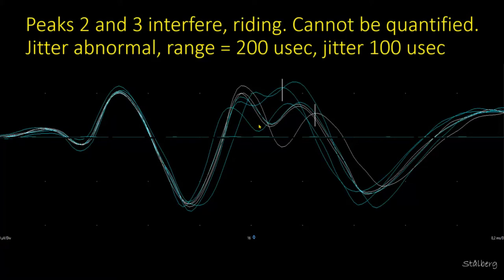Here is another situation where we trigger here with some baseline fluctuation, and the riding is very severe. The first, second, and third peaks are visible. The earliest and latest position of the third signal show a range of about 200 microseconds, which corresponds to a jitter of about 100 microseconds — definitely abnormal.